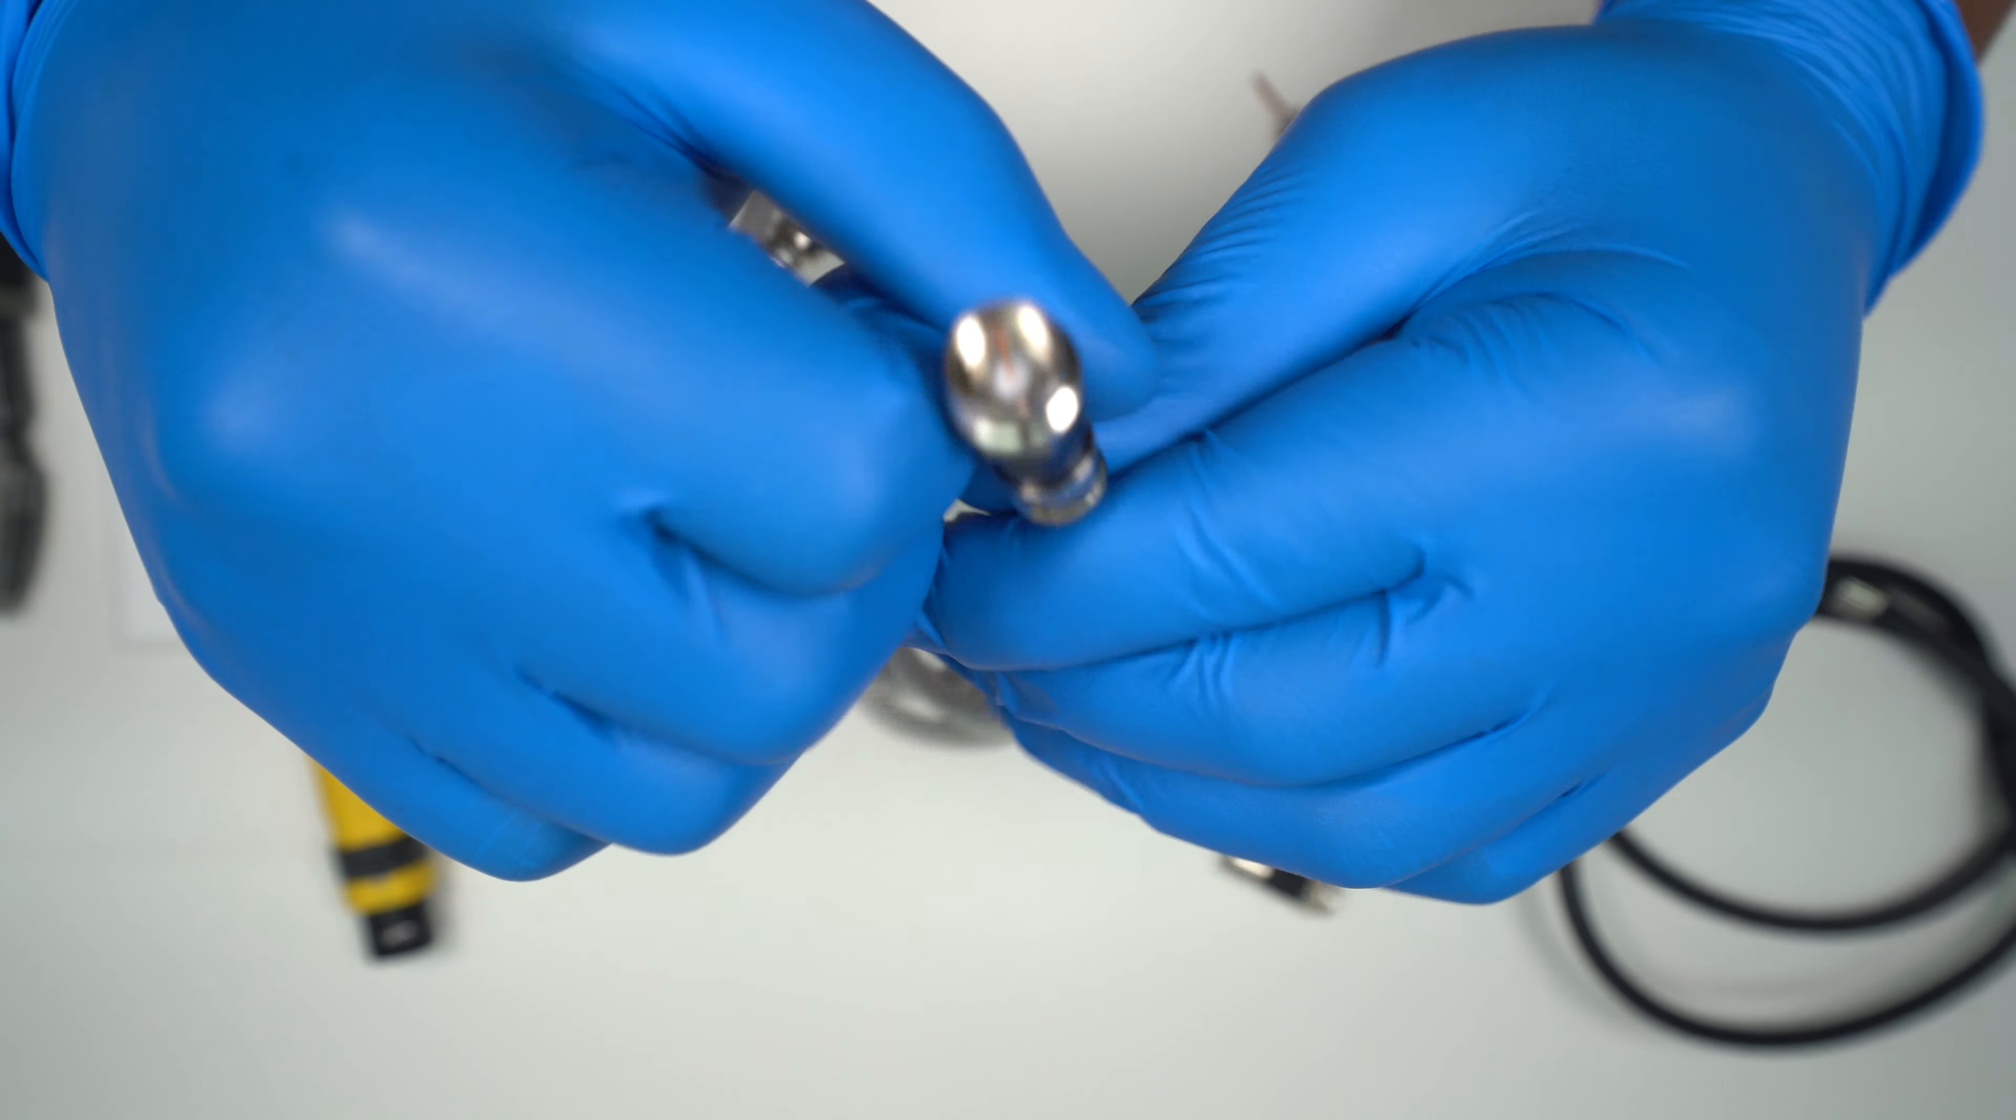Just in case you missed it, I'm just going to show you the difference between an uncrimped and crimped one. As you can see, there's a double barrel here and on here is a single barrel. Now with that being said, sometimes you could come across one that has a double barrel—that means it has not been crimped by whoever was there. The best way to tell is to try and pull it off. If it does not budge, it's been properly crimped.